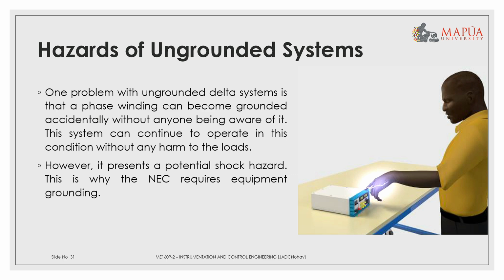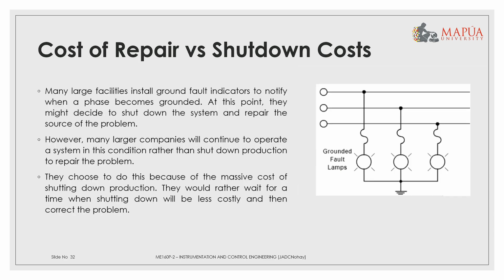So, hazard of ungrounded system. One problem with an ungrounded delta system is that a phase winding can be grounded accidentally without anyone being aware of it. This system can continue to operate in this condition without any harm to the loads. However, the NEC requires equipment grounding. Cost of repair versus shutdown cost.